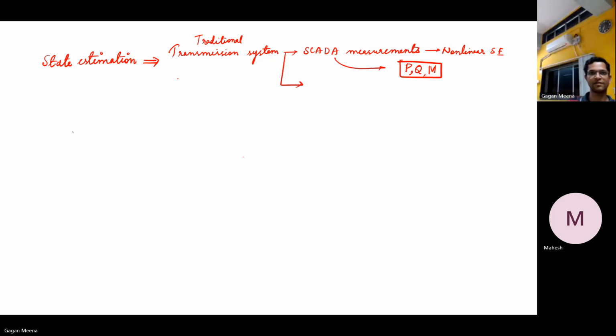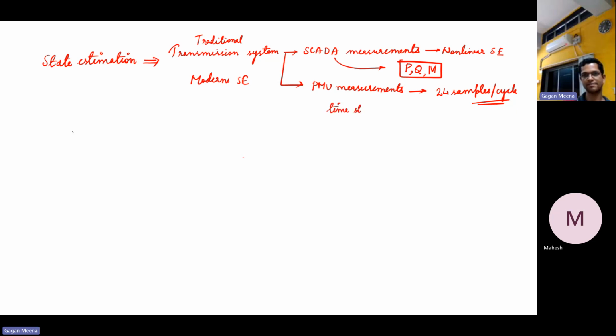Now we have modern state estimators. They use PMU measurements, and they can give us a wide variety of outputs. So they can give measurements at a rate of 24 samples per cycle. And the main advantage here is that the measurements are time stamped, from the GPS signal. So here we directly get the V and theta measurement. We also get f and ROCOF, the rate of change of frequency, df by dt.